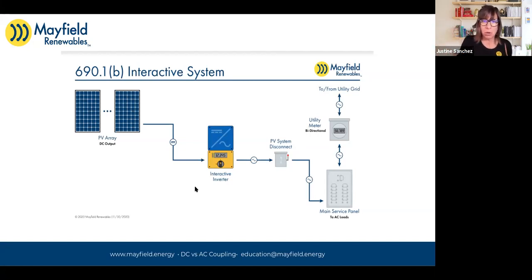Okay. And so it's very common to see, let's keep this in the residential setting for now, let's say we have a 5 kilowatt array, we might put that on a 4 kW inverter. Okay. And so there's a limiting factor here. If we were to produce 5 kilowatts with the PV array, we can't pass any more than 4 through this interactive inverter. Okay, and so that's called a clipping loss. Let's say it was a bright and sunny day, super low temperatures. We are throttled, basically we have a bottleneck. It's okay, it's not going to hurt any equipment. We just can't produce any more than this interactive inverter is rated for.